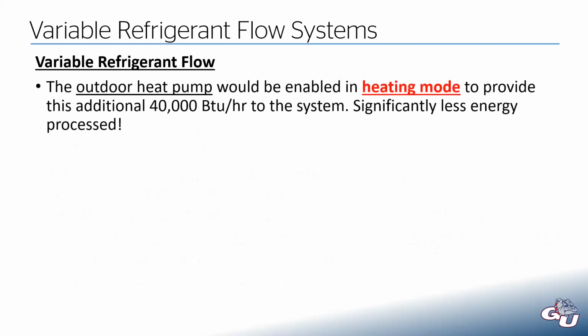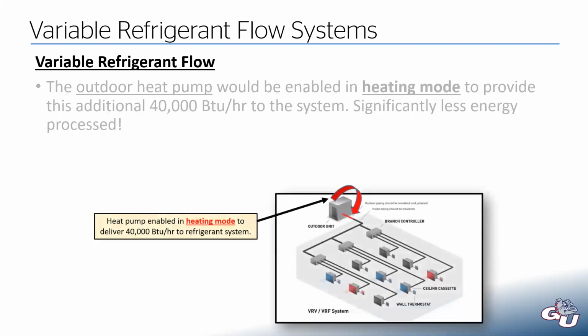So our outdoor heat pump, we would turn that on in heating mode, because that's how we are skewed. That's the mode that our balance is telling us we need. So we turn that on in heating mode to get that 40,000 BTUs to the system. And then the other 80,000 is just shuffled around inside. So we turn on our heat pump, we take 40,000 BTUs per hour from the surrounding air, put it into the refrigerant, and now that's in the network and can be delivered.